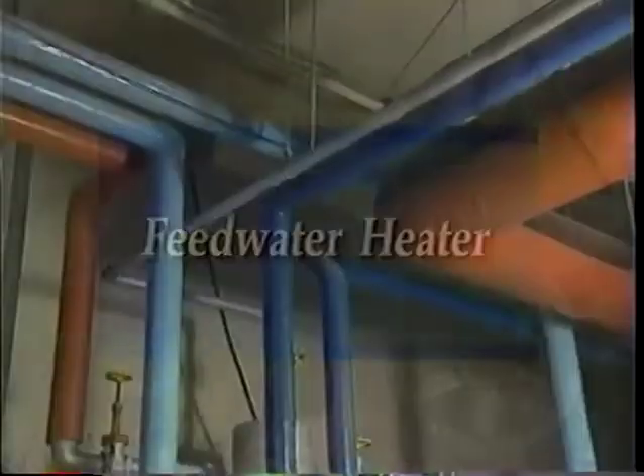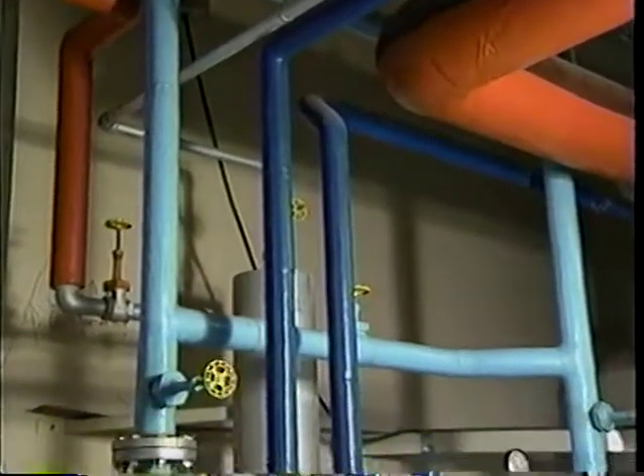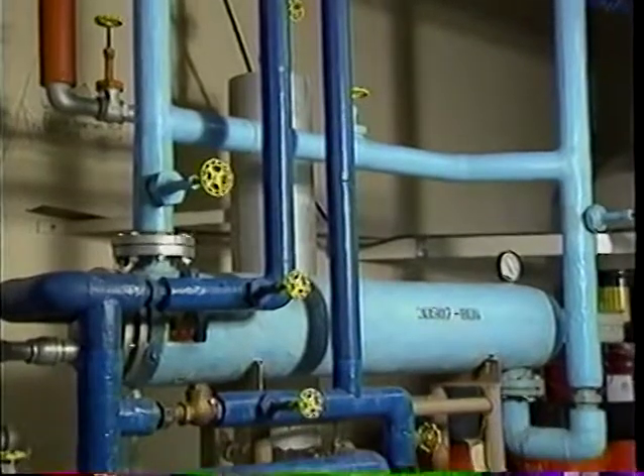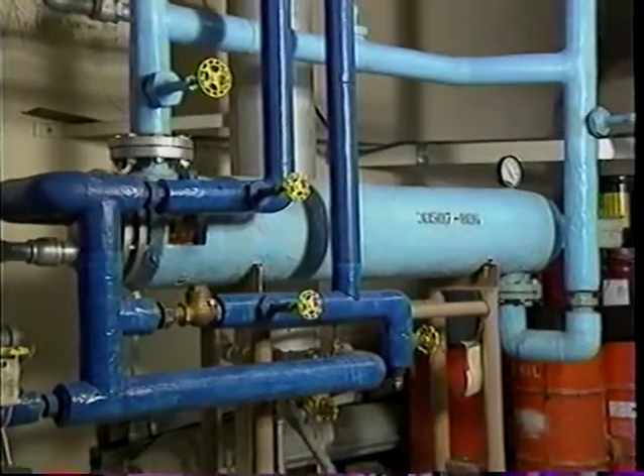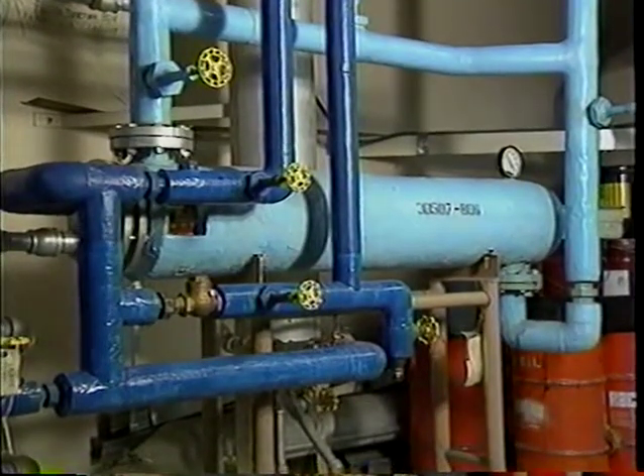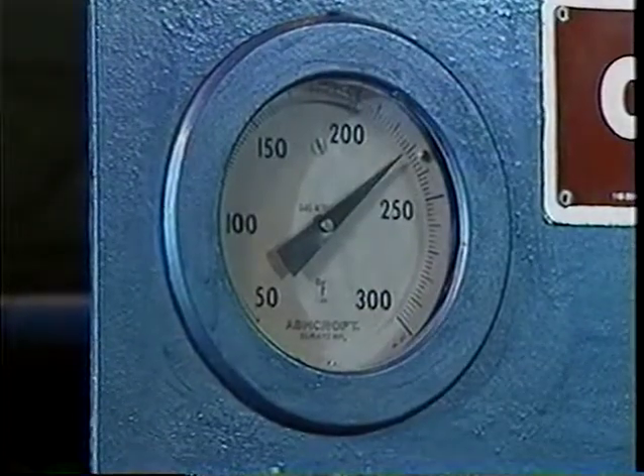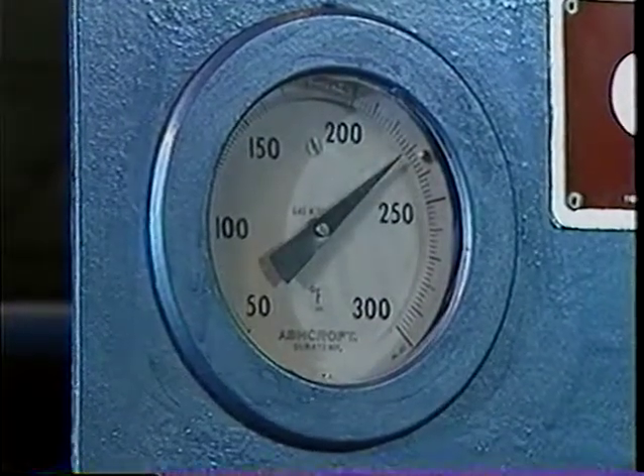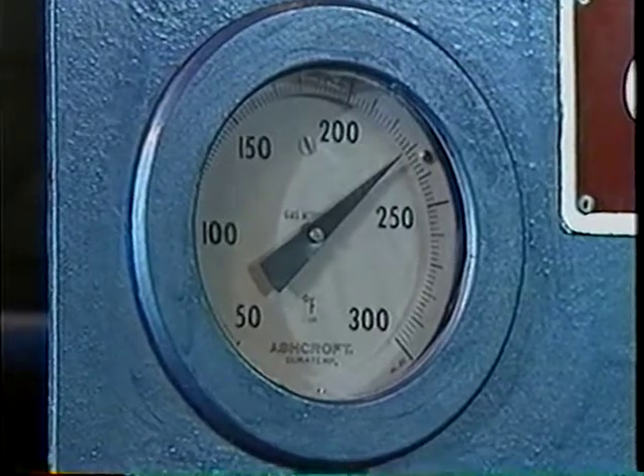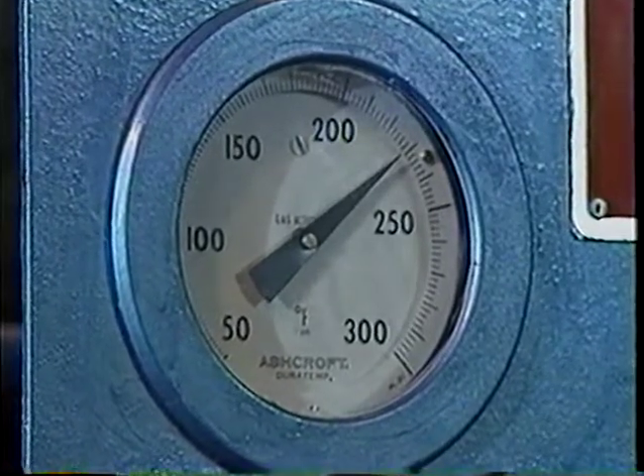Feedwater heater. Feedwater heaters heat water before it enters the boiler drum to remove oxygen and other gases which may cause corrosion. Maintaining the proper feedwater temperature will also reduce the amount of scale-causing salts from settling on the heating surfaces of the boiler drum.